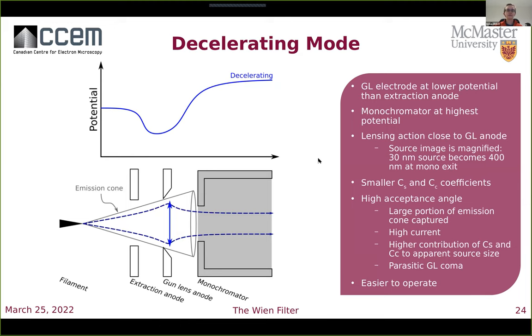In decelerating mode — available on microscopes equipped with an X-FEG, as both our Titans now are — the gun lens anode is held at a lower potential than the extraction anode, and the monochromator is held at the highest potential. The lensing action of the gun lens is close to the gun lens anode, collecting a larger portion of the tip's emission. Because the effective lens is closer to the filament, decelerating mode results in a larger magnification of the source image at the exit plane of the mono. Although aberration coefficients of the gun lens in this mode are lower, spherical and chromatic aberrations contribute more strongly because of the higher acceptance angle. However, this mode gives a much higher current and is easier to operate.